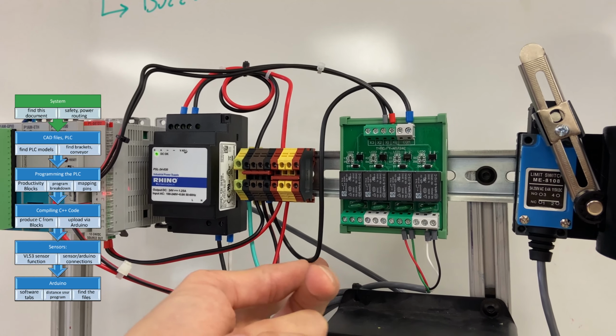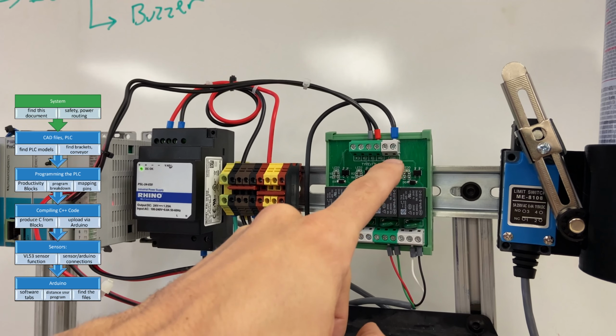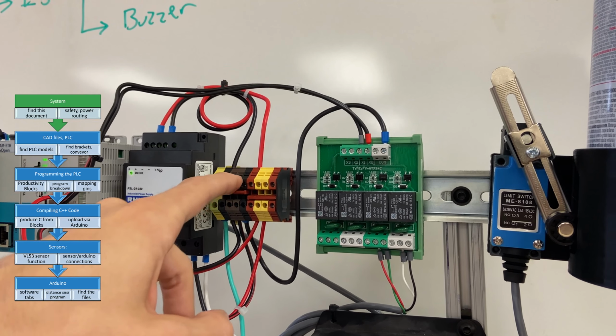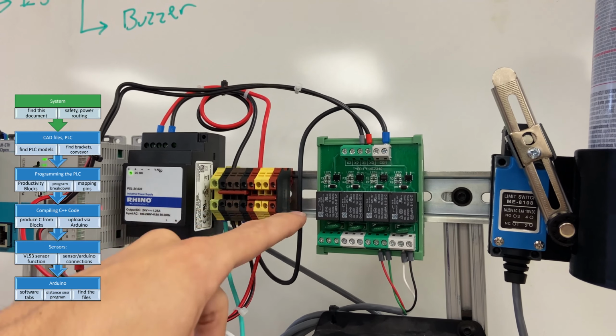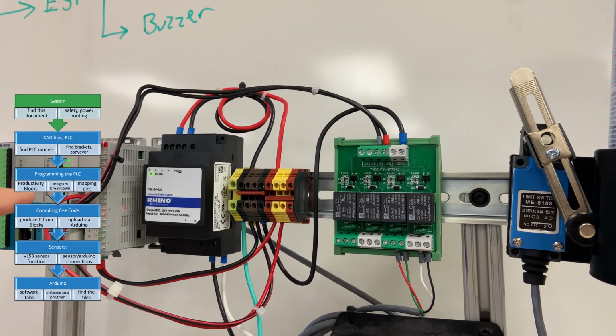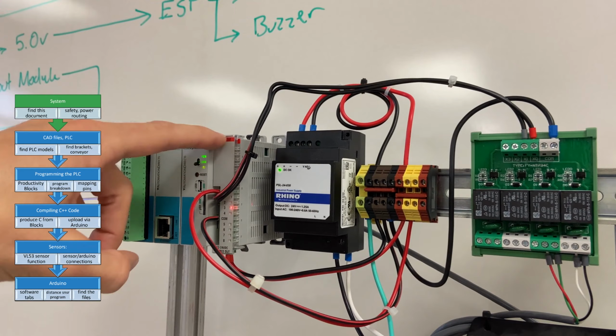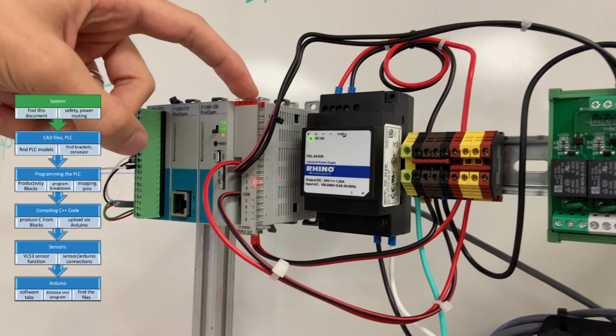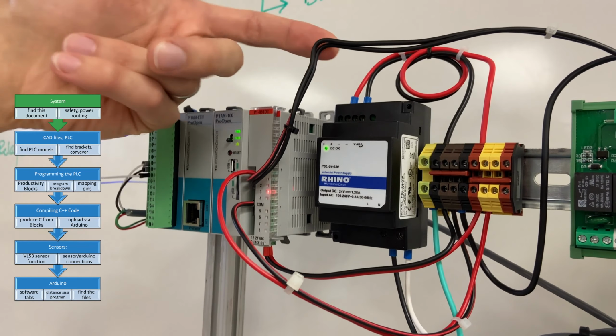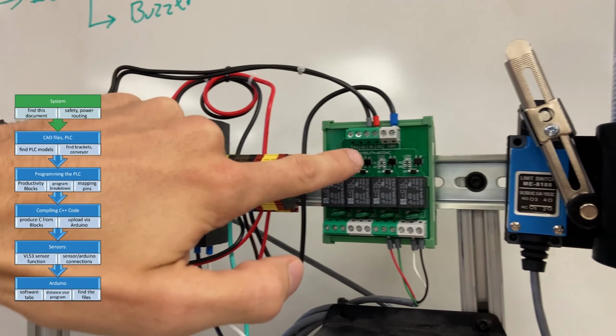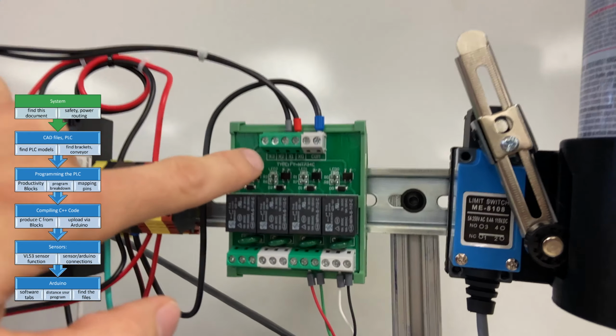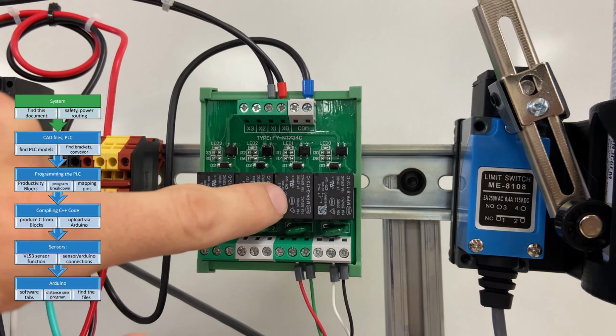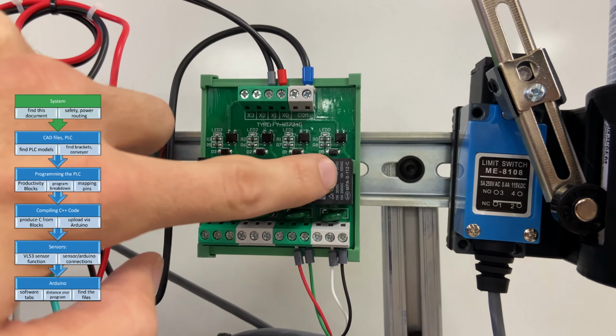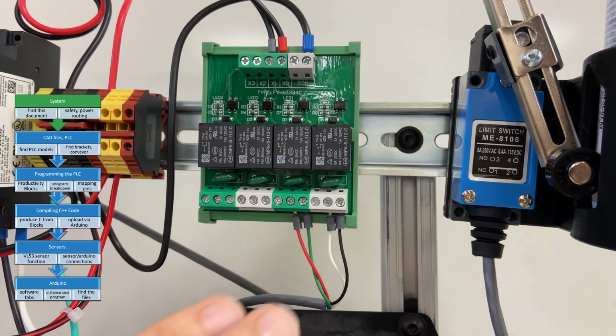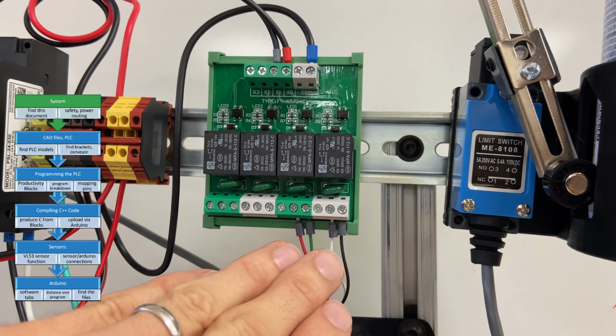So the relay is tied with a common ground to the same ground as the other components through this black wire. And then the signals outgoing from this digital 24 volt module send on these black wires to the input 0 and 1 in order to drive the relays 0 and 1. Then those make the contact on these wires. These wires are not part of the power system.